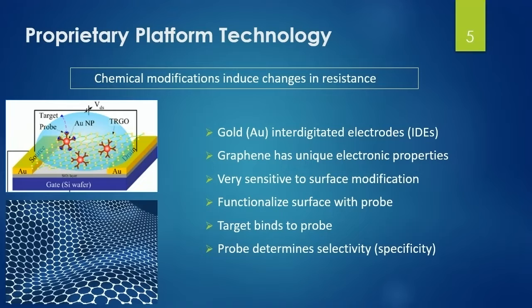This patented technology is predicated on using graphene to bridge gold interdigitated electrodes, and the specificity is controlled by the probe that is attached to the surface. So after we functionalize the surface with the necessary probe, that makes it selective towards our particular target, in this case lead. Graphene has some unique properties that make it perfect for this particular application. It's very sensitive to small changes in the surface, and these surface modifications can cause a change in conductivity or resistivity, which is measured and can be correlated back to lead concentration.